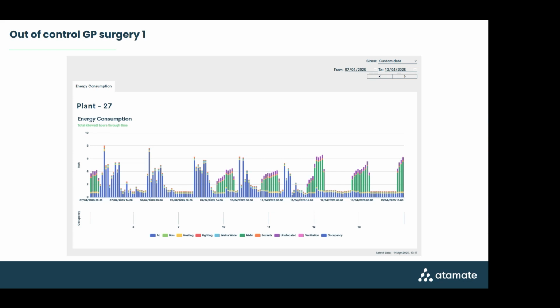In my view, we should really be commissioning buildings for each season - quarterly commissioning - because buildings do change and you need to configure them. No one had picked up on the fact that this building was not being ventilated at all.